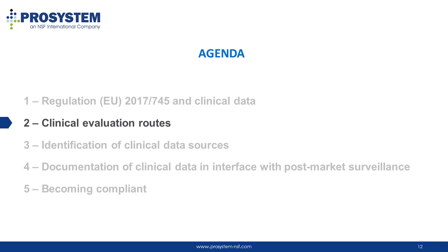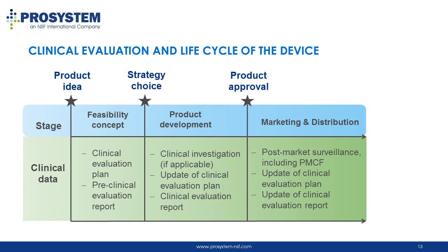Let's now talk about the requirements on clinical evaluation and the routes that can be adopted to conduct it. So, when should a manufacturer start considering clinical data? Basically, since the initial discussions about the product idea. At this point, it is recommended to do a preclinical evaluation, which includes a clinical evaluation plan and a clinical evaluation report.